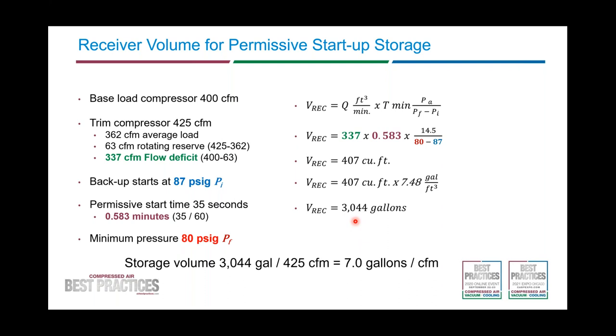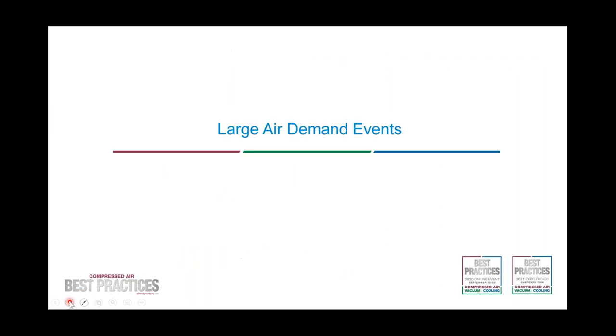You'll notice where the three-to-five gallons per CFM rule of thumb leaves us: this storage requirement for permissive startup time requires seven gallons per CFM of the trim compressor. So the three-to-five gallon rule of thumb is really only for efficient unloading and loading of a lubricant-injected rotary screw compressor. If you want to cover a standby event like an unanticipated compressor shutdown, do the calculations.